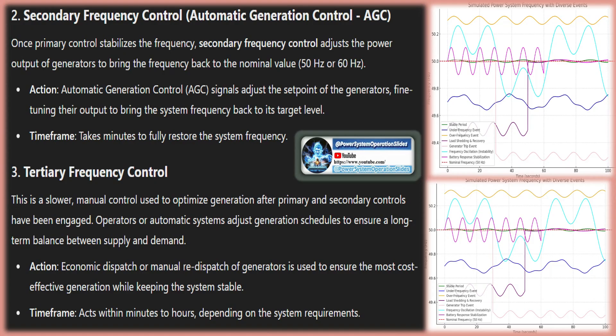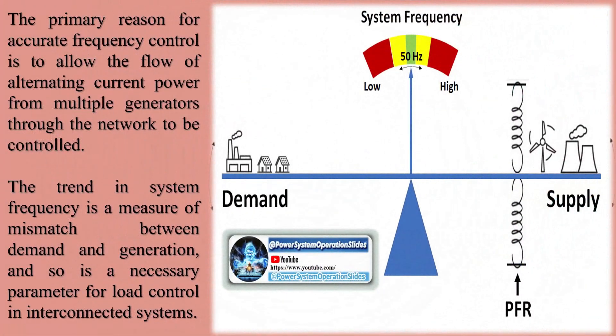The primary reason for accurate frequency control is to allow the flow of alternating current power from multiple generators through the network to be controlled. Frequency of the system will vary as load and generation change. Increasing the mechanical input power to a synchronous generator will not greatly affect the system frequency, but will produce more electric power from that unit. During a severe overload caused by tripping or failure of generators or transmission lines, the power system frequency will decline due to an imbalance of load versus generation.